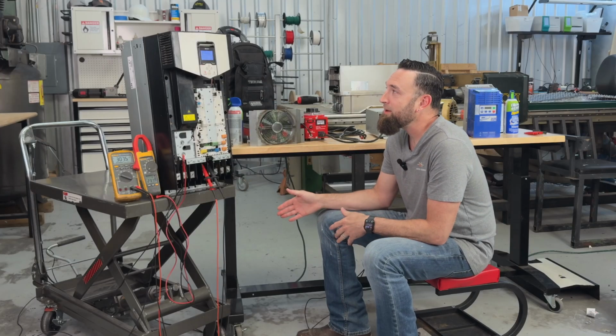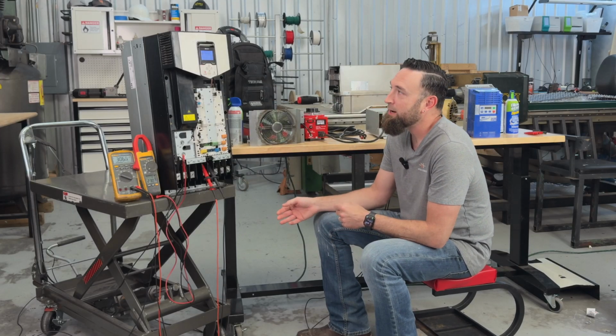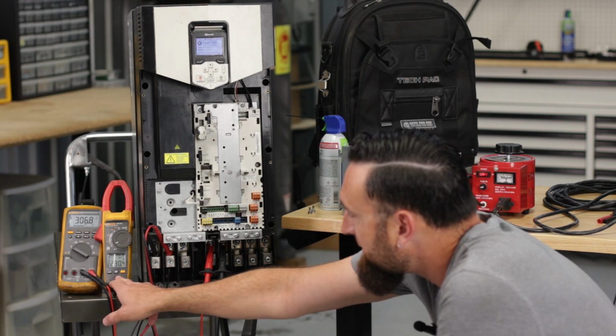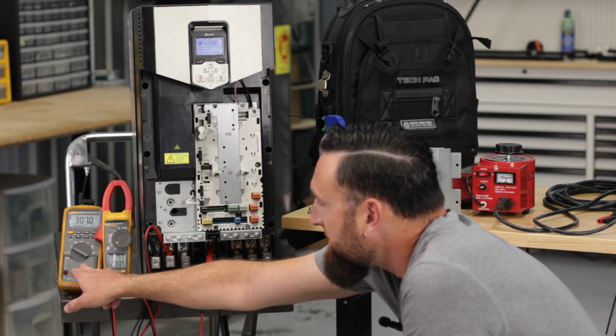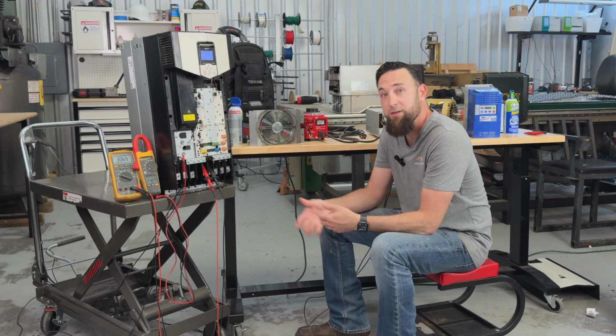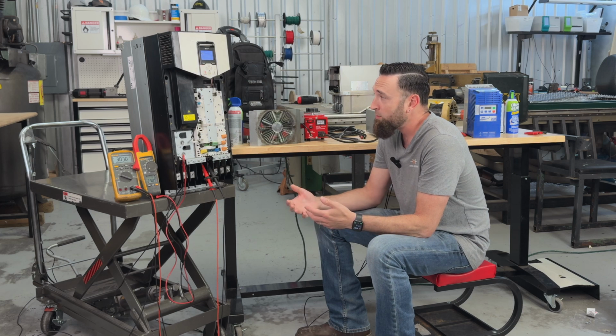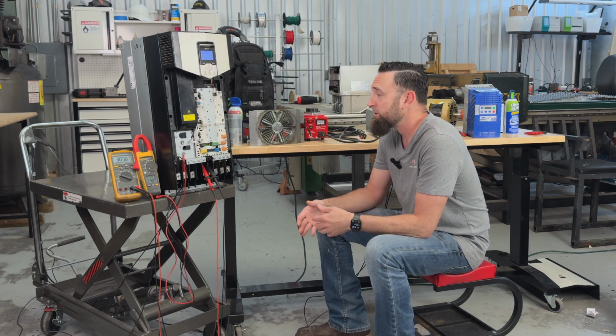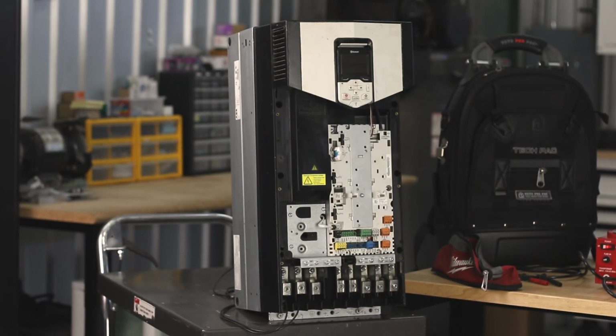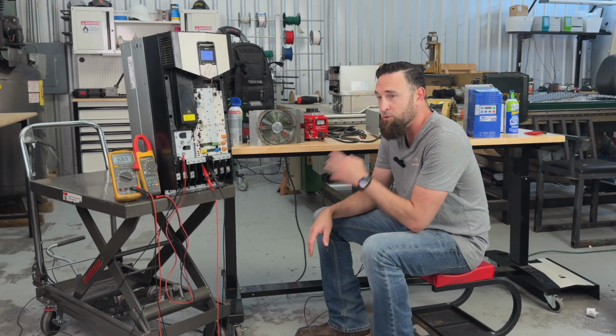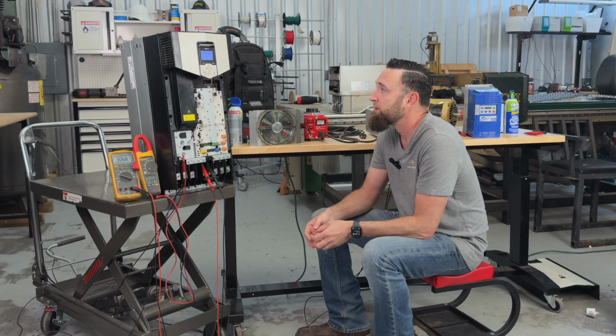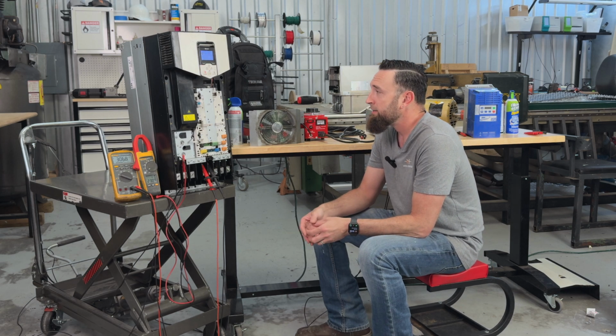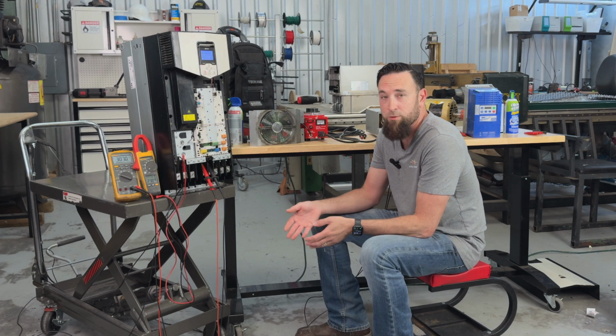All right, our drive has completed powering up. We're at 230 volts AC - there's our AC voltage. Our DC bus is now up to 307. We didn't have any issues detrimental to this project. The capacitors sounded good - no arcing or popping, no surging from the transformer or the Variac. But we did encounter one issue we wanted to talk about.